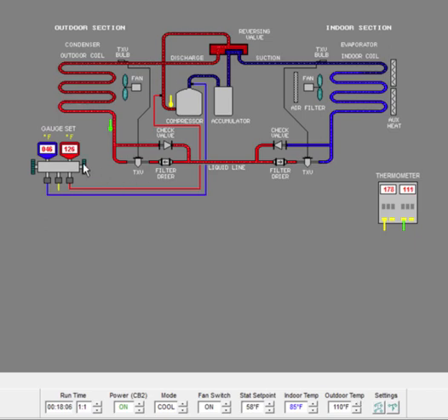Notice what's happening in my condensing temperature. It's going up. Okay, the higher the outdoor air temperature, the higher my condensing temperature is going to be. But what have we done with the difference between the two? Okay, now at 27 degrees. Has it affected it a little bit? Yeah, it has.